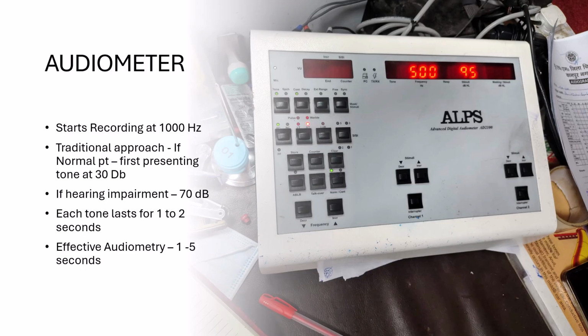So, audiometer settings and protocol. When you begin PTA, you start at 1000 Hz, the frequency most easily heard. If the patient is likely normal, start at 30 decibels. For someone with hearing loss, start at 70 decibels to ensure they hear the initial tone. Each tone should last for 1 to 2 seconds, and the ideal presentation is between 1 to 5 seconds, not too fast and not too slow.